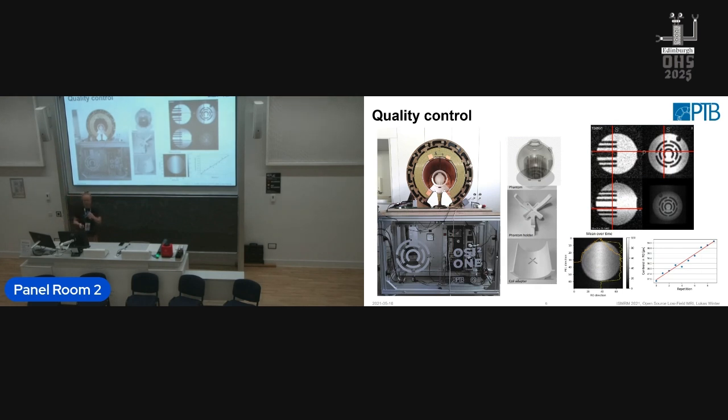When you have that, you can run some first imaging experiments. Then you start with some simple testing objects, but that's important because you also have to have a quality control somehow, so that if someone reproduces it, you get similar results and you can evaluate: did I do a good job? Is my SNR how it should look? Or if I exchange components, because it's a very modular approach, how we try to set it up, that you maybe exchange your amplifier, RF coil, or whatever, what's the difference between my results?